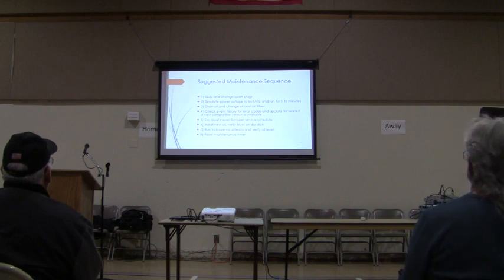I've worked around a lot of generators, and you've got to have pretty nimble fingers for a lot of them. Simulate a power outage if you have a transfer switch and run for 5 or 10 minutes. You don't have to do this, it's just annual maintenance.